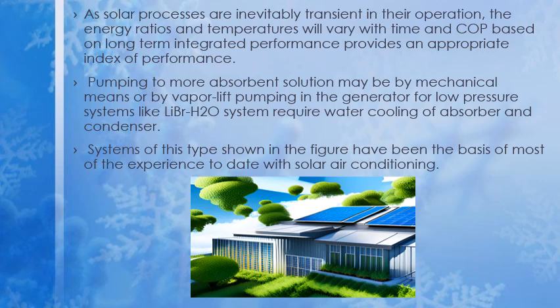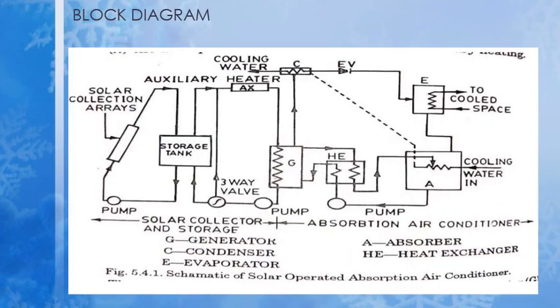Common practice in solar experiments has been to use water-cooled absorbers and condensers, which in turn requires a cooling tower. So we can consider this the explanation of the working of solar space cooling of buildings, that is vapor absorption air cooling using the lithium bromide water system up to 85 to 95 degrees Celsius. This is the block diagram for the working of the solar space cooling of buildings. We can see here a pump, a storage tank, heat exchanger, auxiliary heater, and cooling.